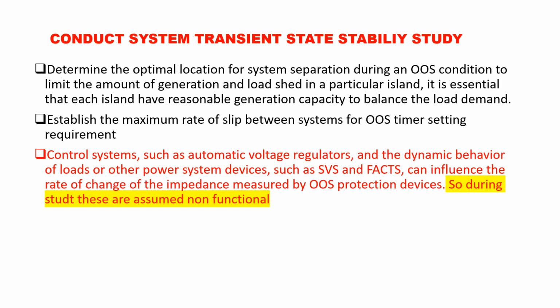Now we determine the optimal location of system separation. See, already I have mentioned this. For saving from the out of stepping of the generator, we can always find the location from the system studies, and then we can separate the system. Then another very important thing is that we can use automatic voltage regulators, and we can use the SVC, the shunt devices, and the FACTS, that is the flexible AC transmission systems, where you can have the shunt power fed into the power system. So static var compensation, SVC, and things like that we can do. That will also help in the improvement of the system stability. This is a kind of protection from the system going out of step, and resulting in the total or partial breakdown of the power system.